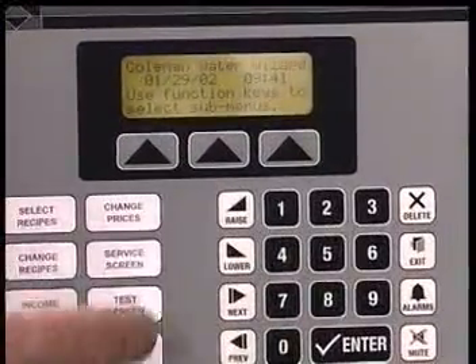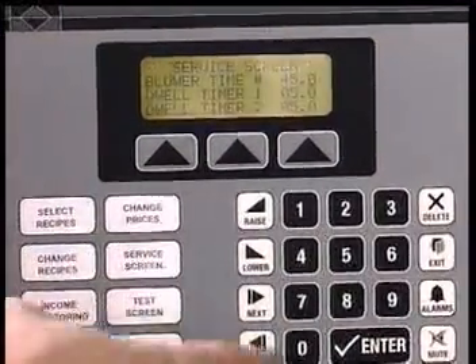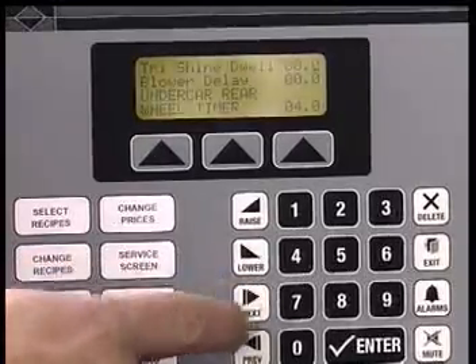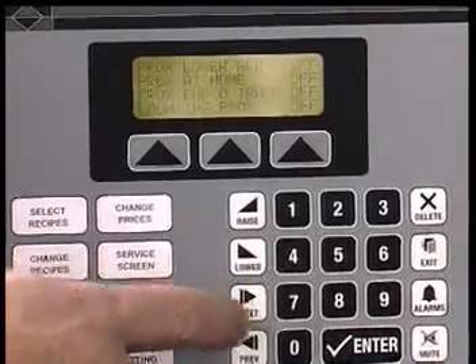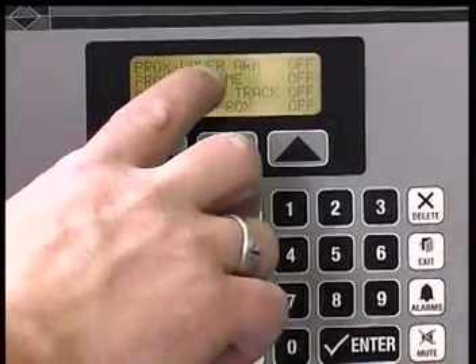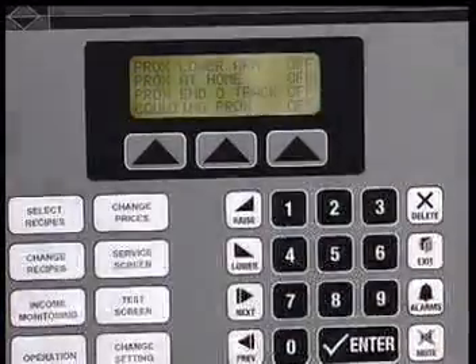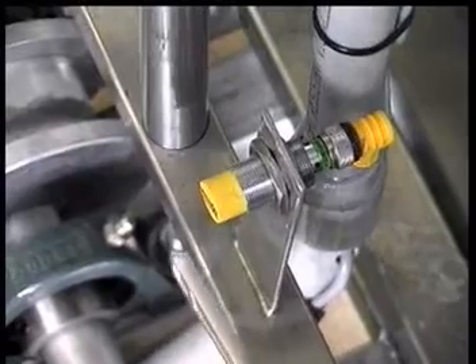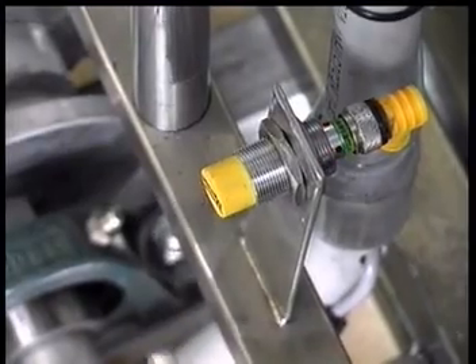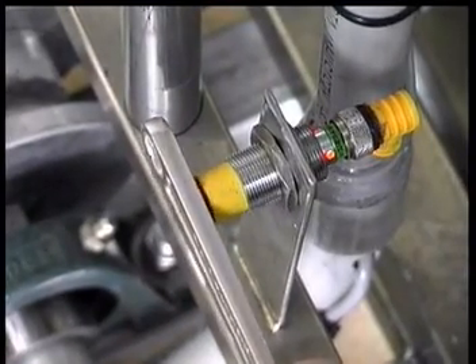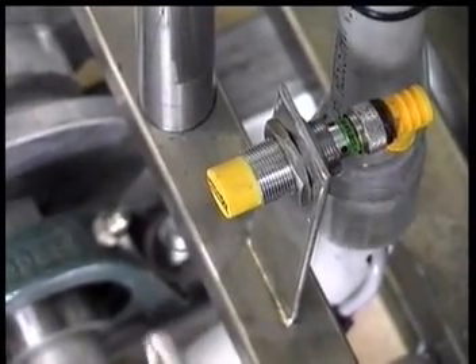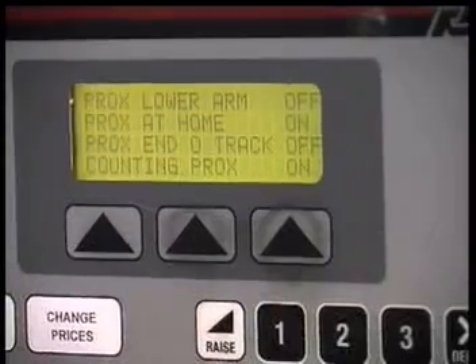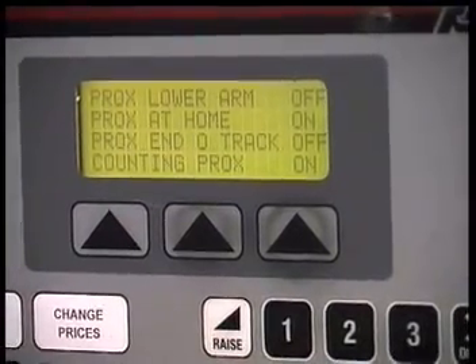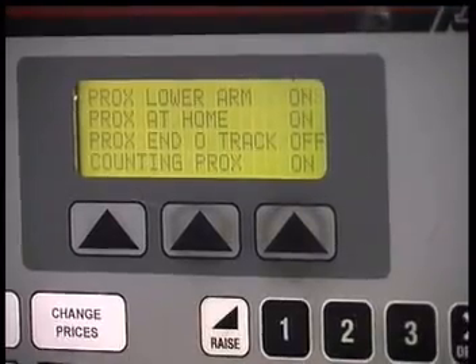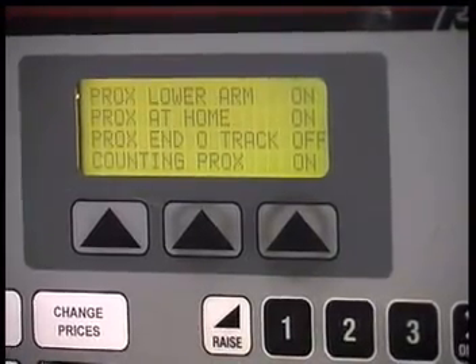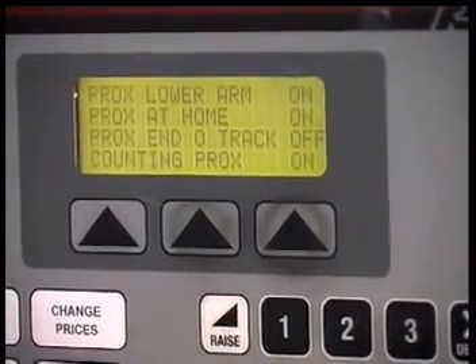The first test of a prox is to determine if it is going on and off. Go to the service screen and scroll to the prox you wish to test. A list of their normal at-home status is listed in the operator interface panel section of the manual. If the prox has power and is working, an LED light on the prox will light when metal is near. When the metal is removed, the light should go out. The next step is to view the on-off status of the same prox on the service screen.